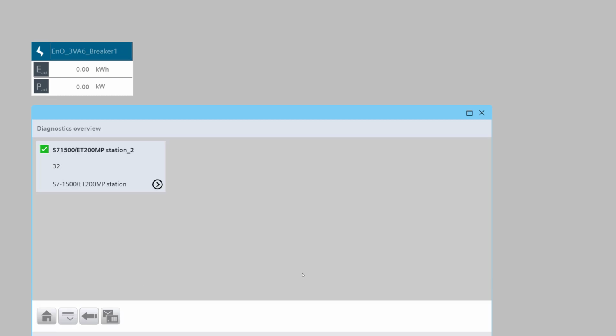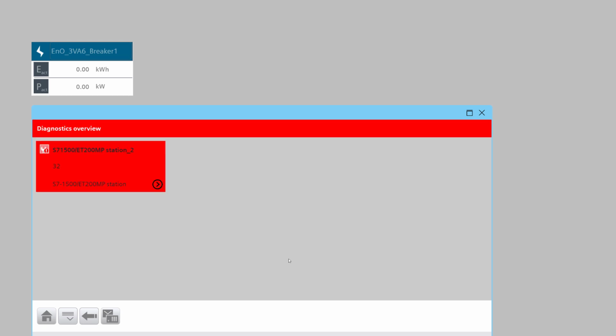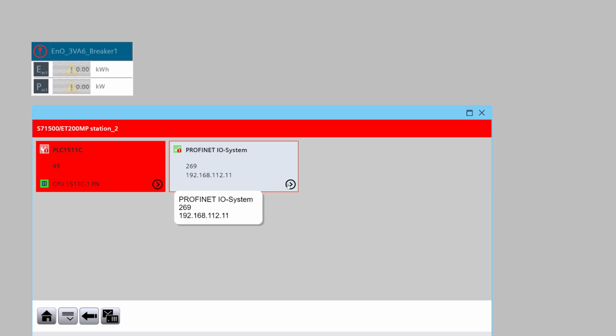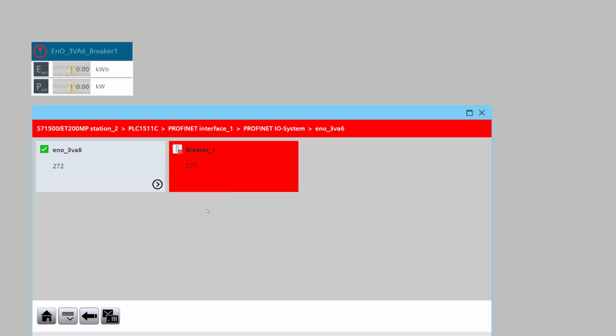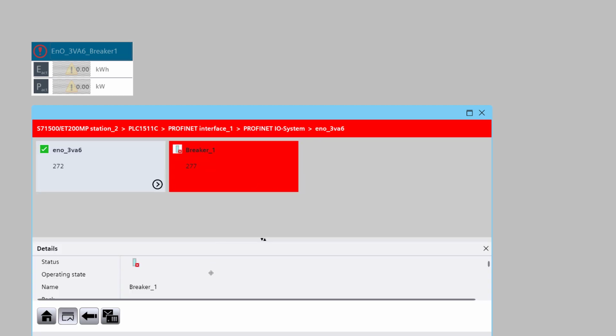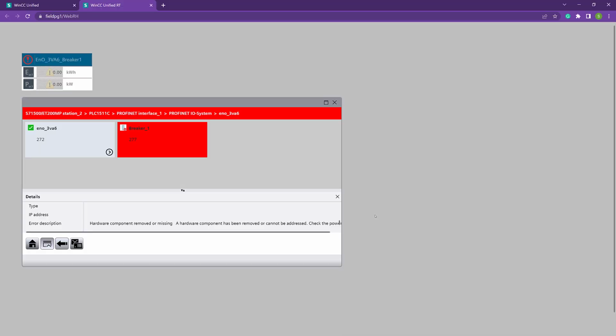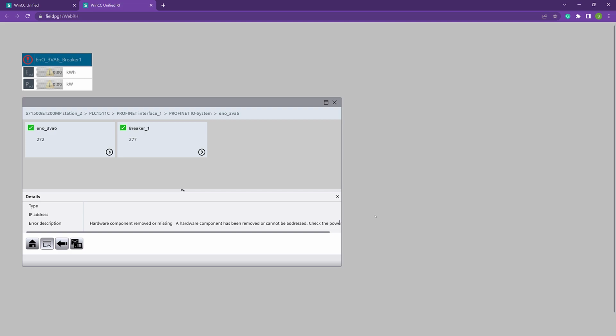So why not? Let's go ahead and generate the same alarm again. I'm going to pull the cabling out of the station here. I pretty quickly found that breaker 1 was in error. And again, we have a hardware component that's been removed or missing. Plugging the cable back in remedies the error.